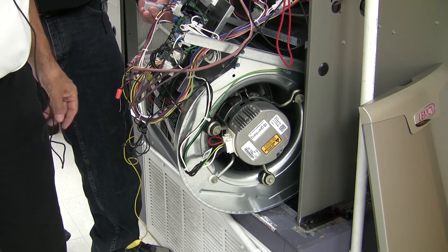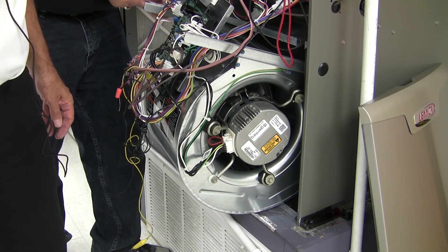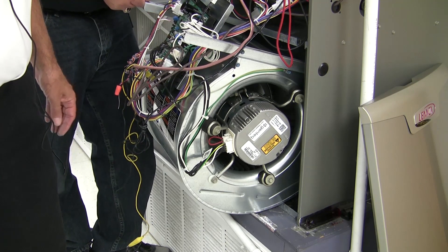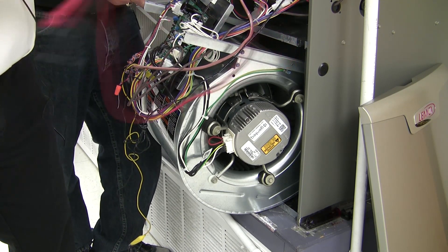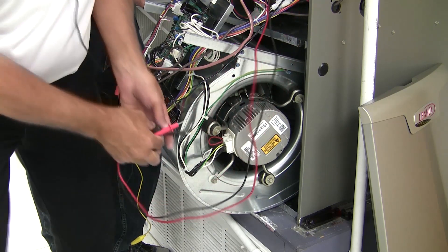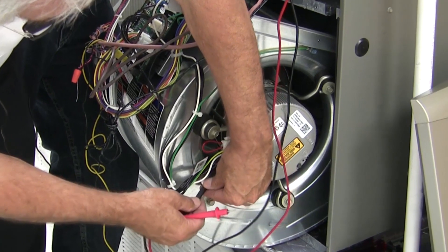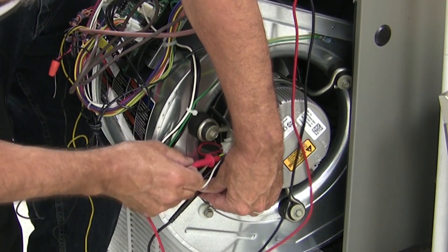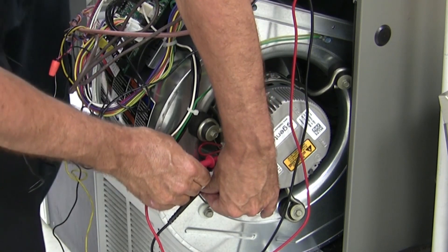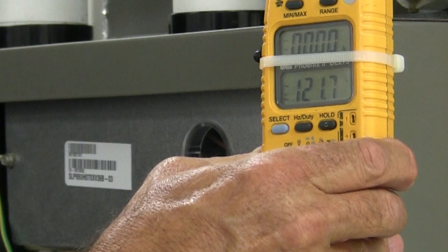What we're going to show today is a couple ways to check our variable speed motor. We're using the 3.0 Regal Beloit motor. First thing we want to do is verify that the high voltage is on the motor. To do that we get our pins and as long as we've got small enough leads we can get in between here when it is still plugged in just to verify the high voltage — and we have 120 volts.